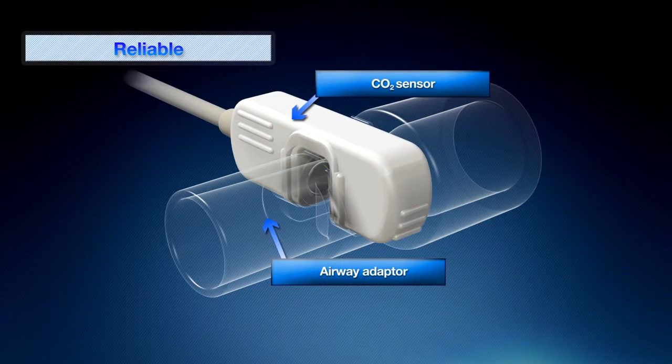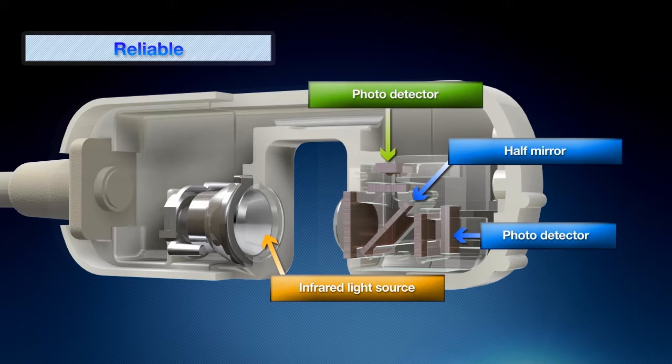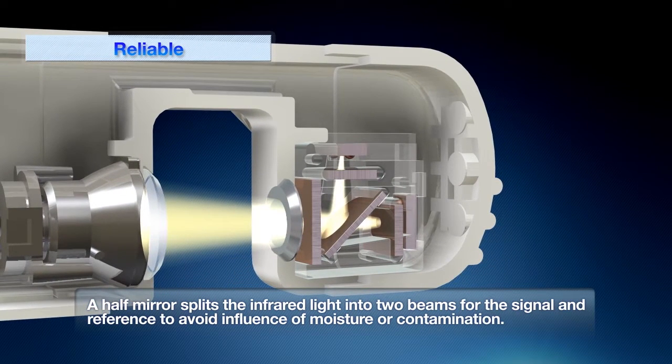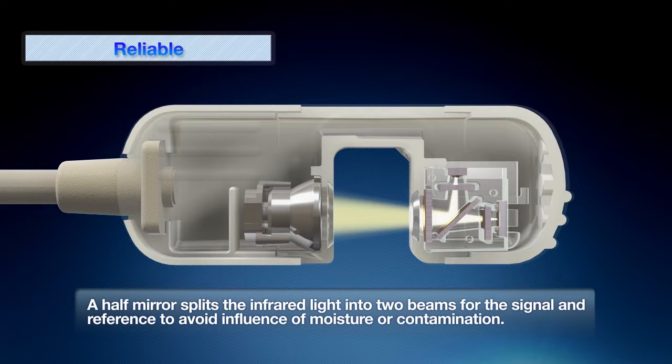cap-ONE has a unique design with just a light source, a half mirror and two photo detectors. Neither a motor nor a heater is required. With this unique structure, cap-ONE realizes accurate and reliable measurement without being affected by humidity or secretion in the airway.